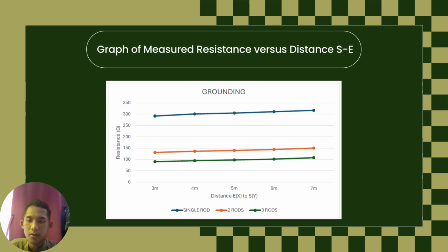The blue line shows the single rod, and it sits at the highest, with a resistance level around 300 ohms. When we move to the second line, which is two rods, the resistance drops by more than half, maybe around 150 ohm until 100. And then the green line, which is three rods, provides the lowest and most efficient grounding, at around 100 ohms.